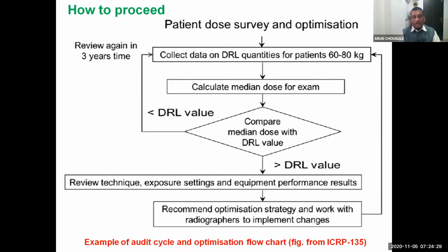So collect the data on diagnostic reference level quantities for patients of 60 to 80 kg. Calculate the median dose from the examination, and then compare the median dose with existing DRLs, if there are any. If your median dose for the examination is exceeding the DRL value set for the country, then you have to review your diagnostic technique, exposure setting, and the equipment performance results to find out why you are getting doses higher than the DRL. And then recommend an optimization strategy and work with radiographers to implement the changes.